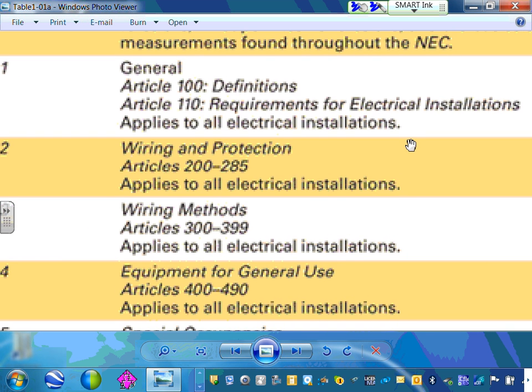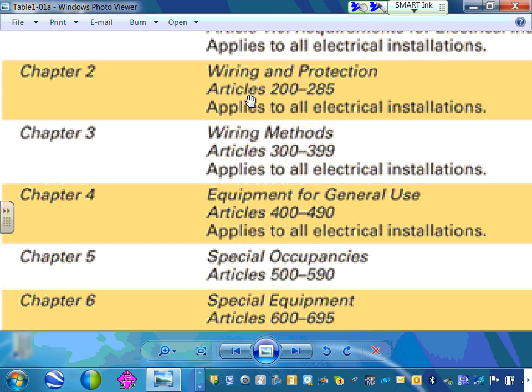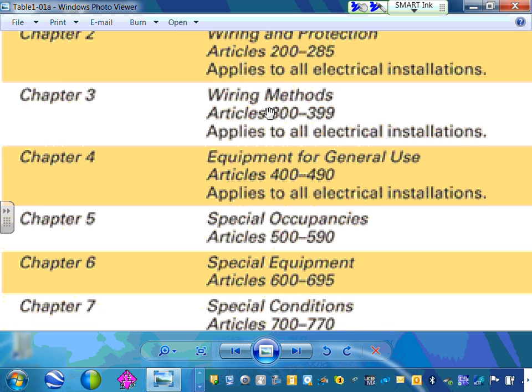Requirements for electrical installation will tell you that you need, say, 3 feet in front of a piece of equipment—3 feet clearance, the width of the equipment for clearances, very important. This applies to the installation. Wiring and protection talks about overcurrent protection devices, branch circuits, feeders, and so on—service, feeders, branch circuits, overcurrent protection devices.